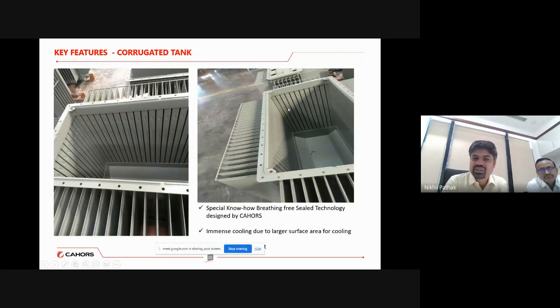And secondly, in a conventional transformer, oil goes out from the top outlet pipe, drops down into the radiators, and from the bottom of the pipe it comes inside after it gets cooled down, so the oil has to follow a travel path from top to bottom. However, in the corrugated, hermetically sealed transformer, oil has a horizontal axis. So oil does not need to follow the path of going top and coming down from the bottom. Since it is open throughout the height, the oil gets cooled down instantly with the larger surface area for cooling. So this is the point we explain.